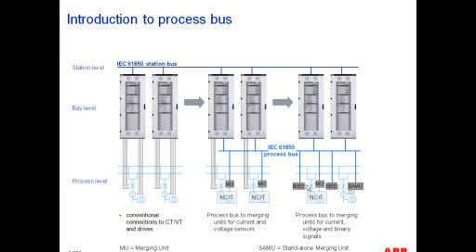Then if we go to a 61850 process bus type architecture, what we're going to find is that from your current and voltage transformers, there are going to be connections to your merging unit. And then from the merging unit, there's going to be an Ethernet network that's used to transmit these current and voltage samples. And then the relays inside our control house would be able to subscribe to those data streams and operate their protection functions based on that. And then there could either be conventional wiring to trip the breaker, or it could be via GOOSE messages, based on the capability that the circuit breaker has.